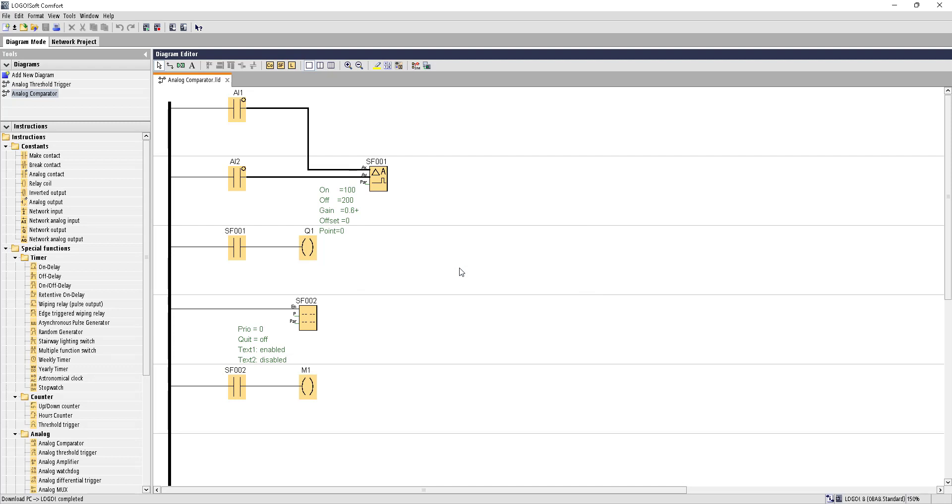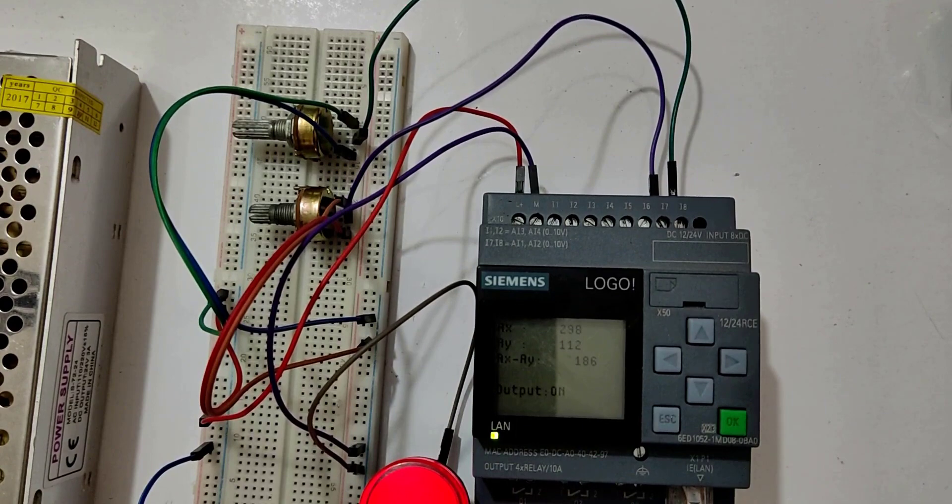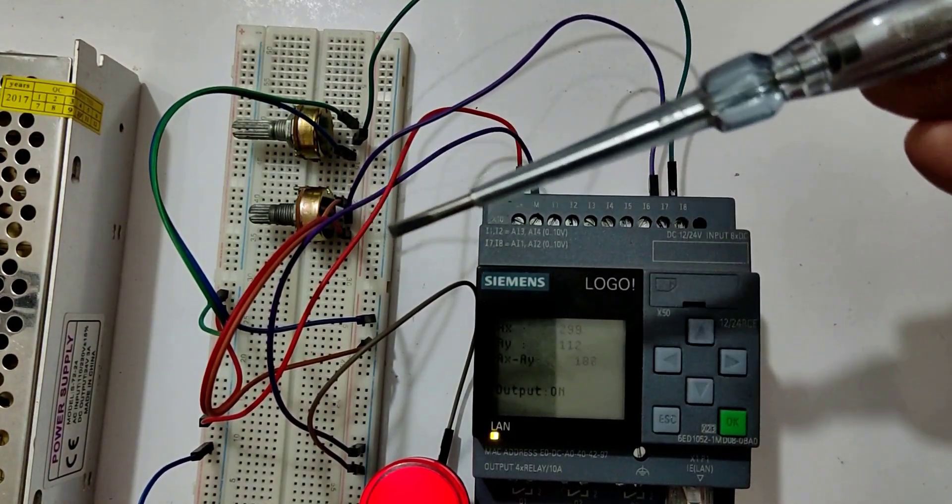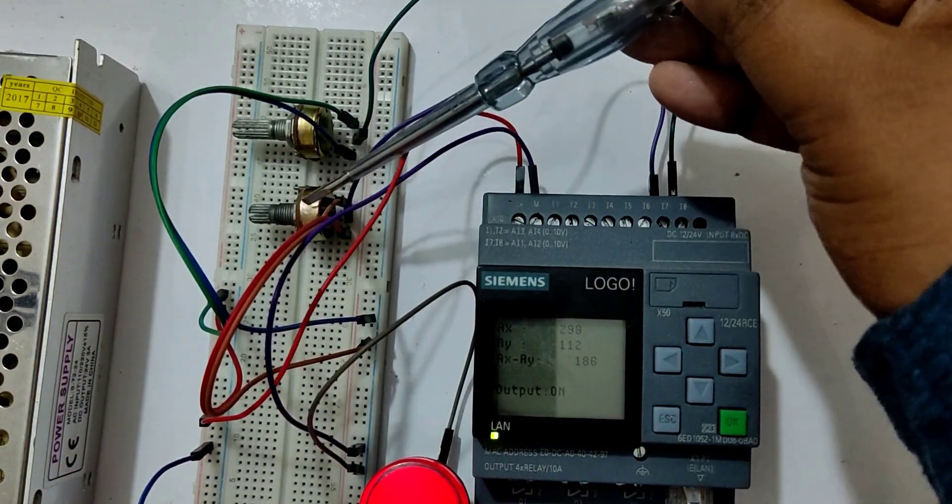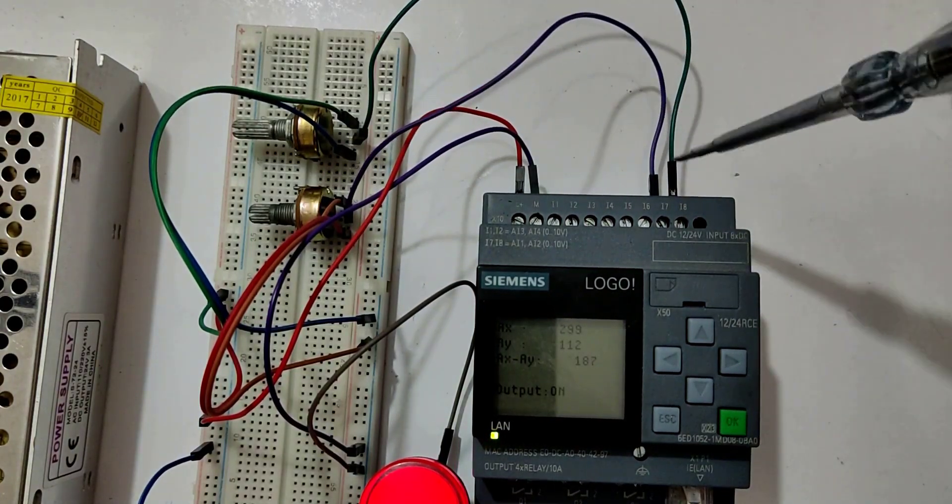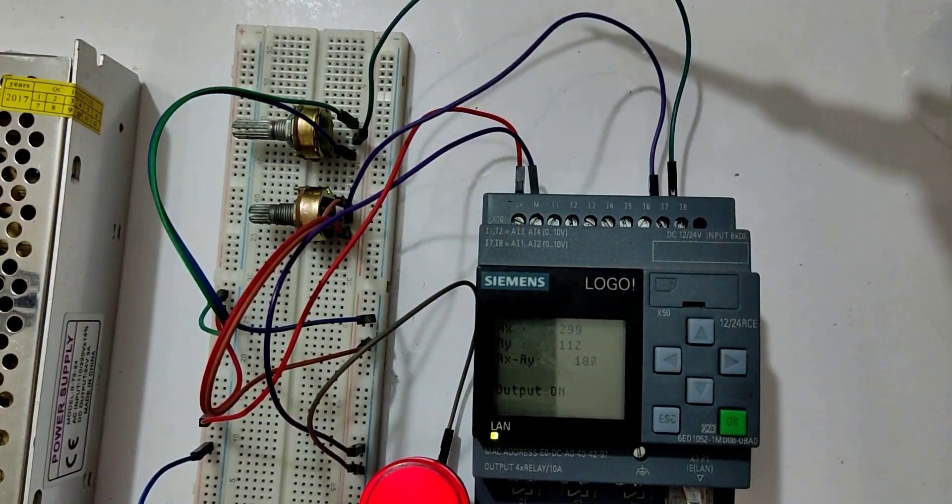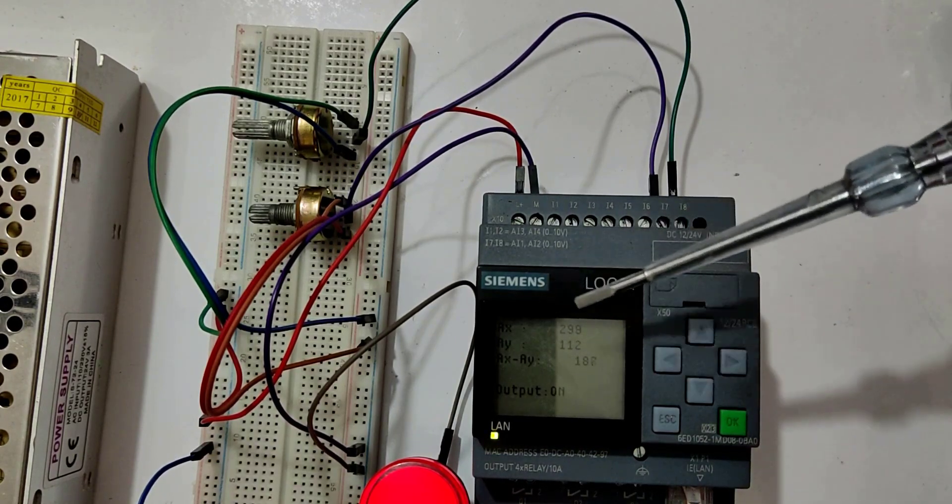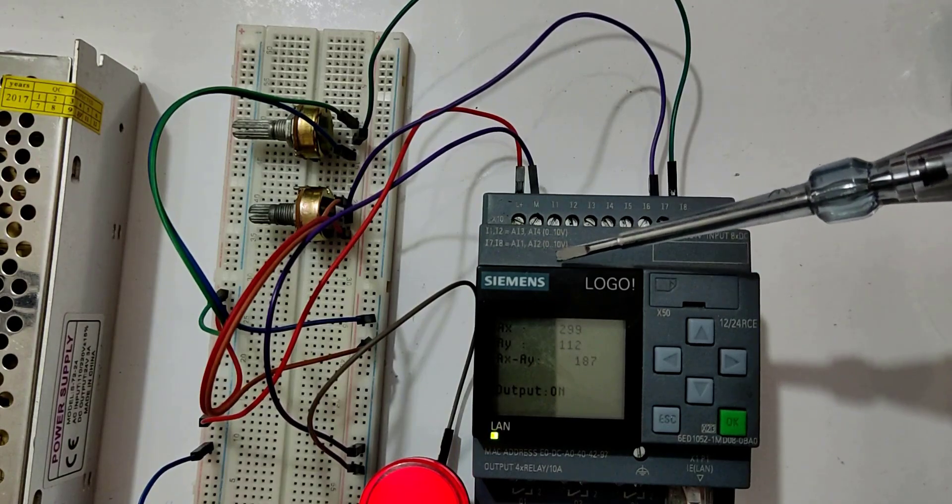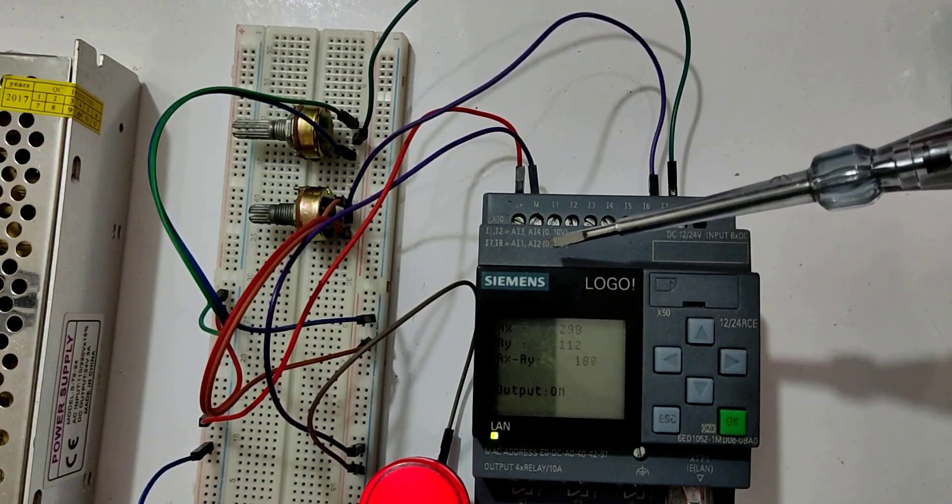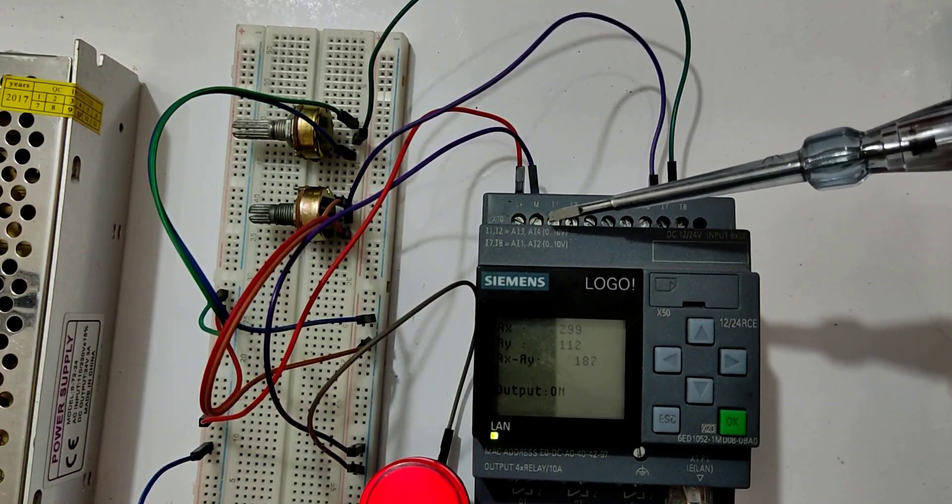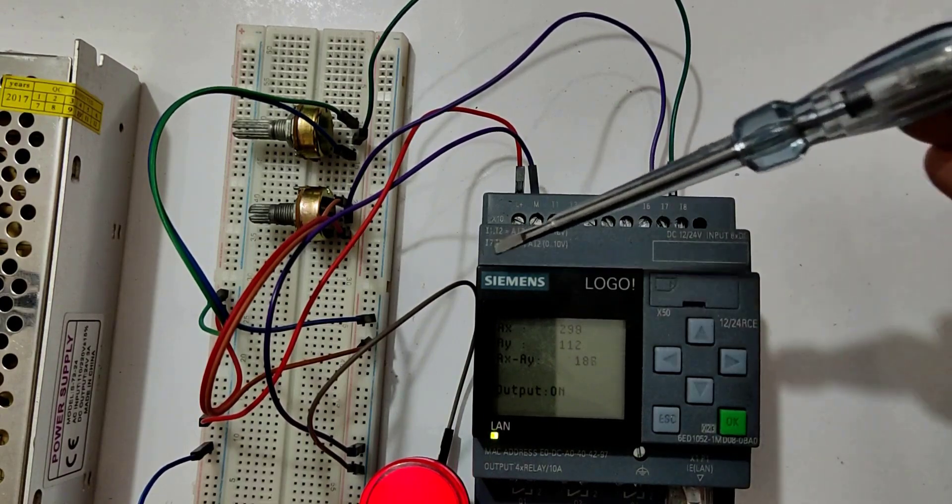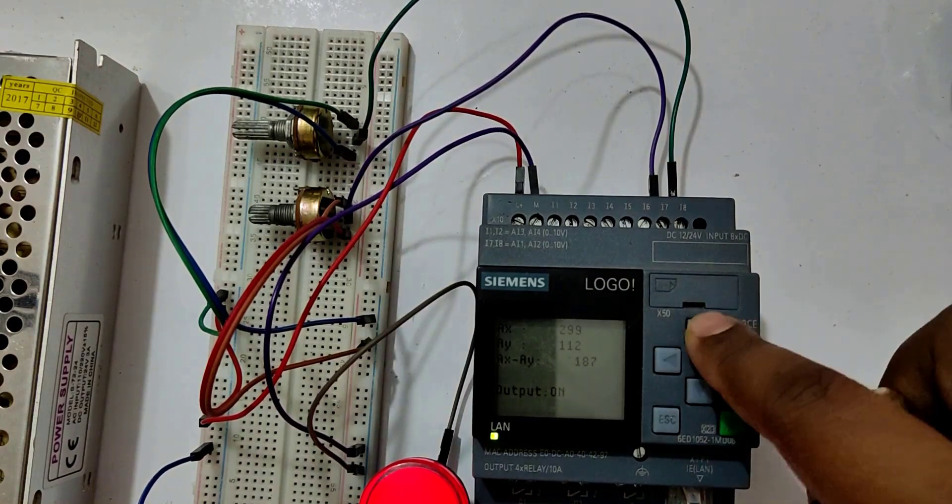Hello guys, this is the hardware demonstration part. For our hardware demonstration, we need two analog sensors. So here are two potentiometers that we have used as analog sensors. This is sensor one, this is sensor two. The output of this sensor, that is the variable point, we have taken our wire and inserted it into our I7 point, and from the second sensor we have taken a wire and we have inserted it into I8. Because for this PLC, I7 and I8, it is mentioned that I7 would be AI1 and I8 will be AI2. We can also use another two analog inputs like I1, I2 for AI3 and AI4. So for this demonstration we have used AI1 and AI2 at I7 and I8 port.